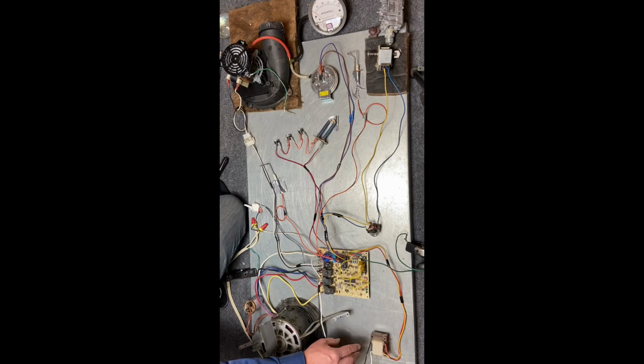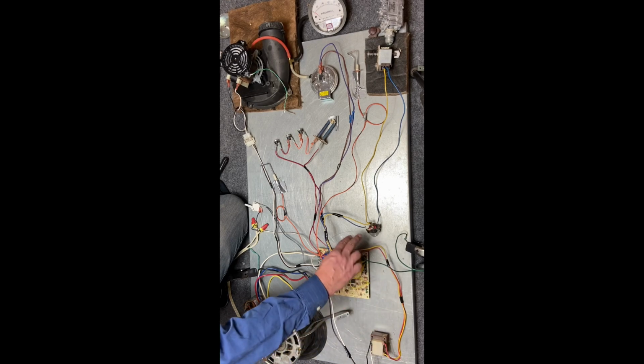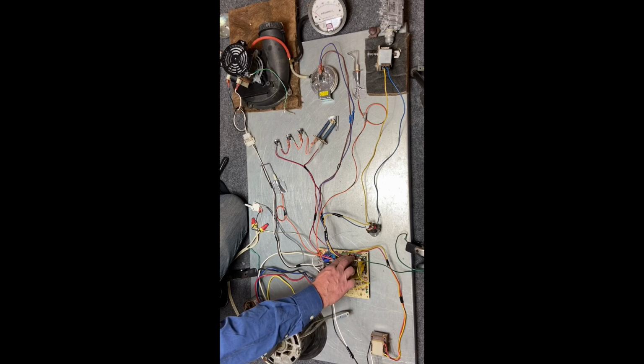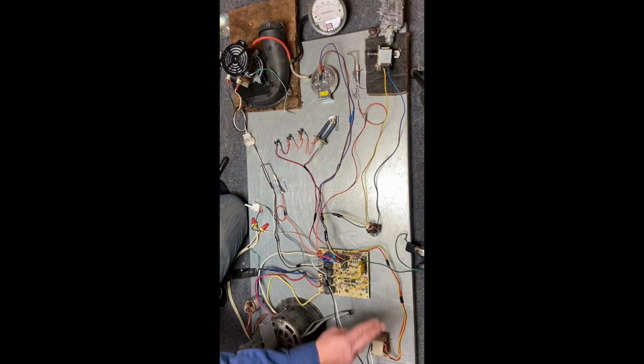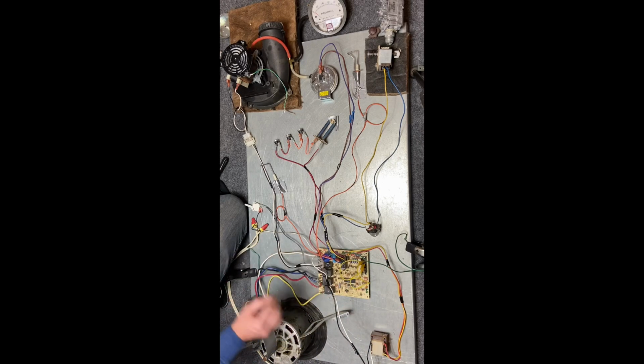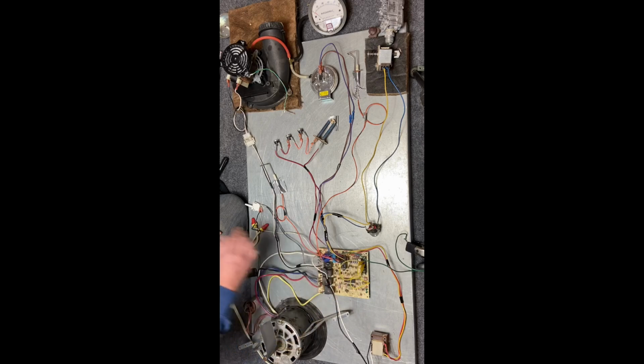Now the job of the transformer is to step it from high voltage down to low voltage, or secondary voltage, or 24 volts. And I say 24 volts loosely because it could be anywhere from 18 volts up to 28 volts. So here's our secondary voltage, and it connects on the board where it says SEC. These 2 wires. 2 wires in, 2 wires out. So if I want to see if my transformer is working, I would check: I have 120 volts going to it, and I have 24 volts coming out of it.